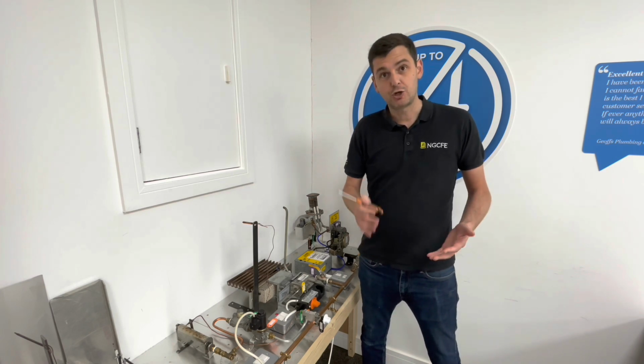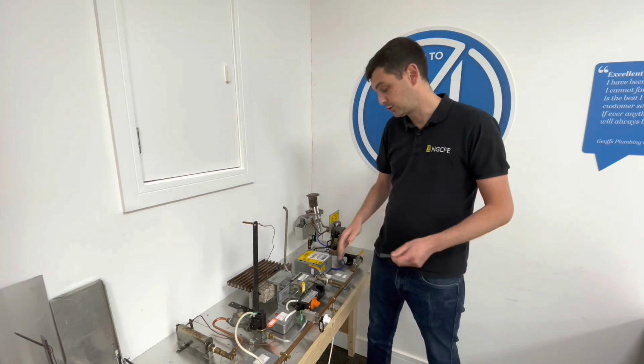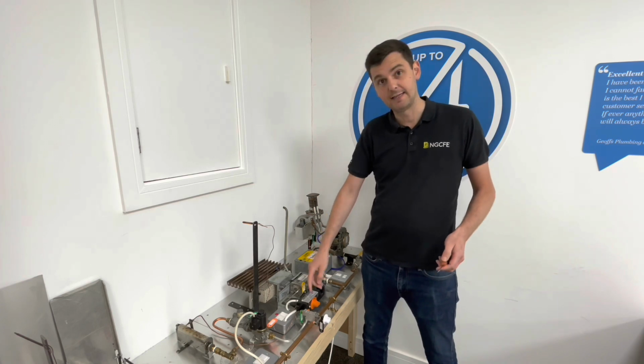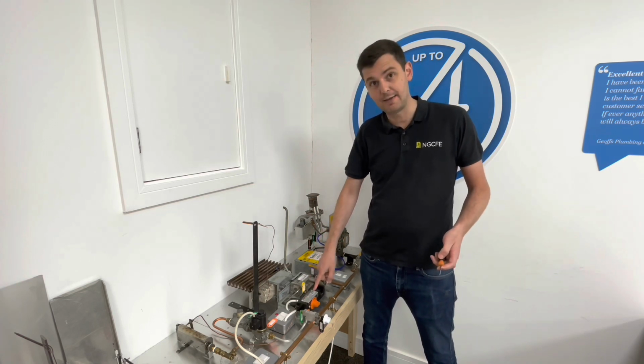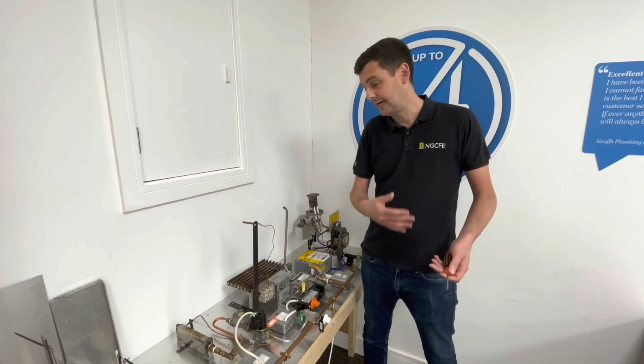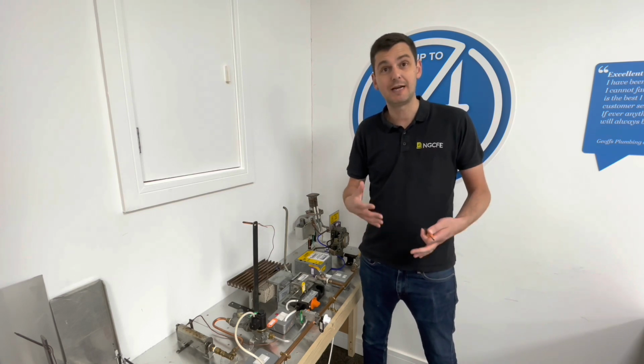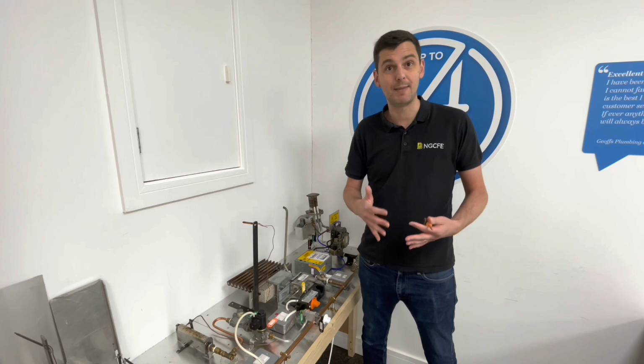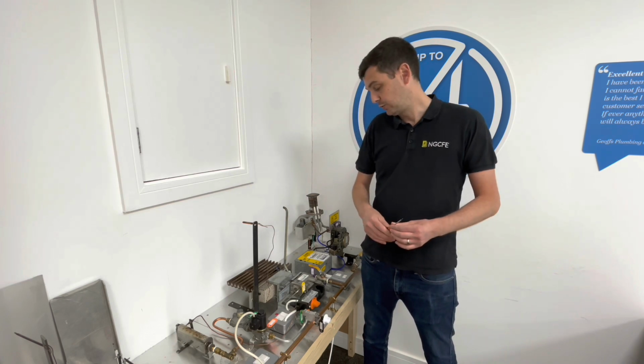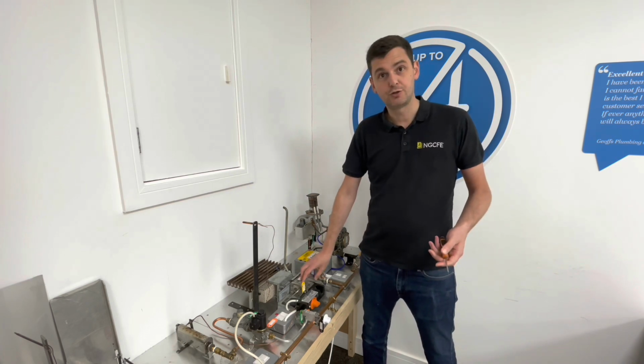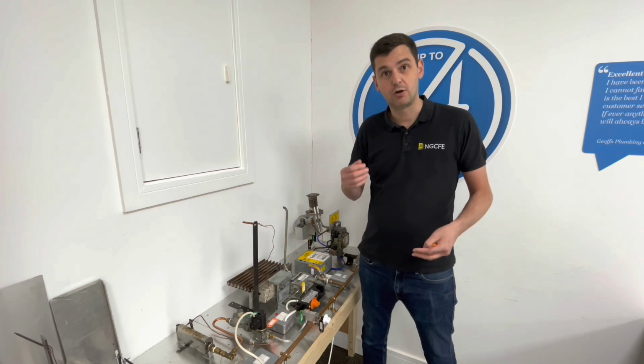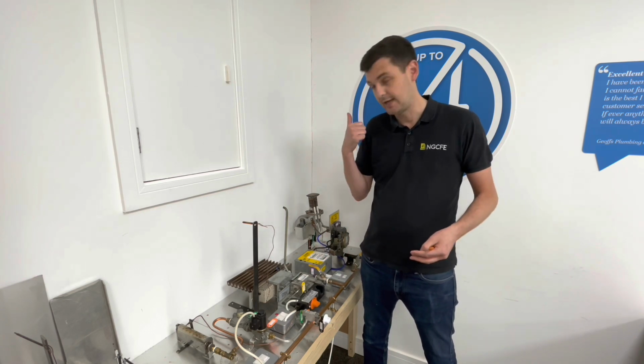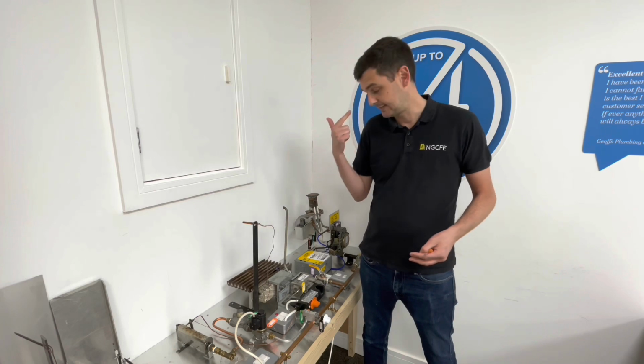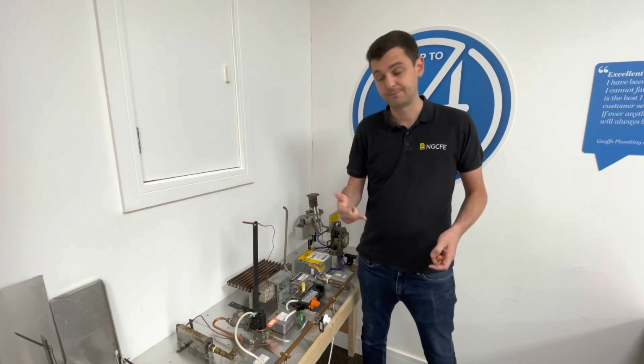It also incorporates a solenoid valve. So the solenoid valve is in this section here, and when the electric thermostat, which we'll talk about in a minute, allows electricity through, it will energize the solenoid valve and allow gas through to the main burner. So again, multifunctional control valve, three main components. It's got a regulator, it's got a thermoelectric valve, and it's also got a solenoid valve.